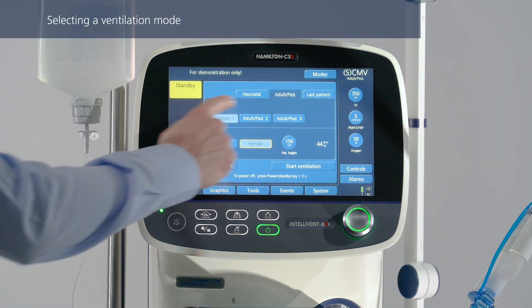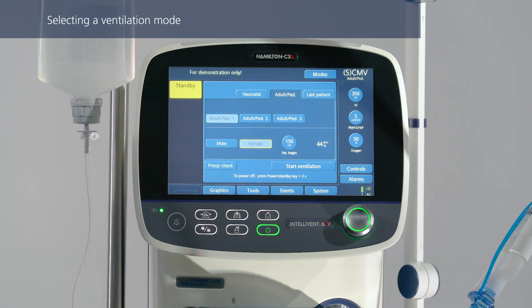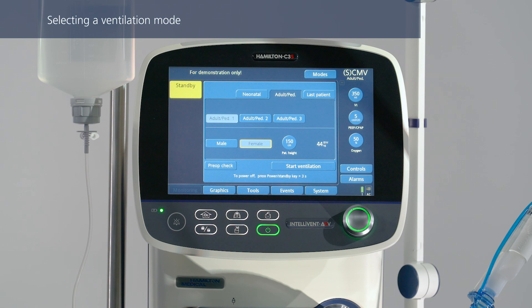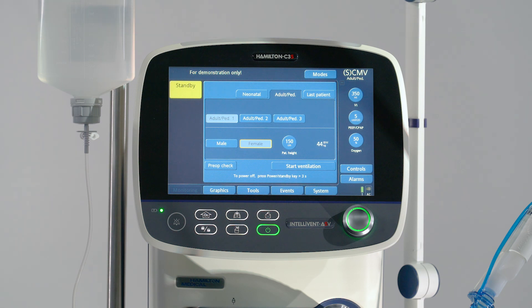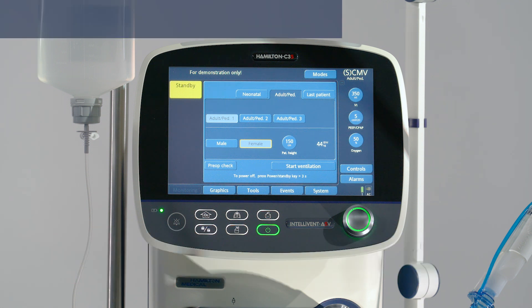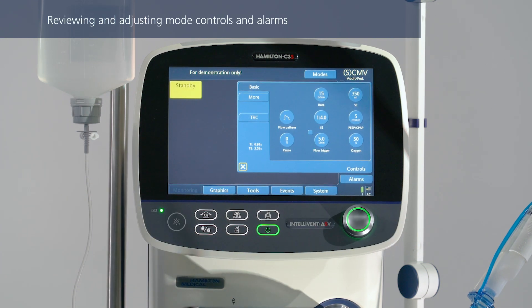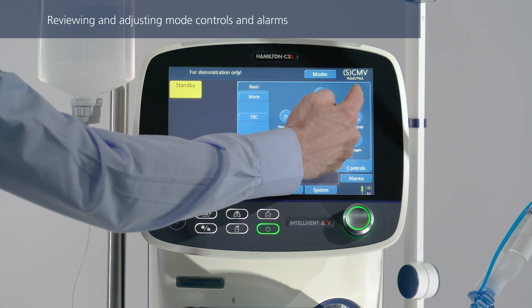For a new patient, you can pre-configure the ventilator quickly just by touching a quick setup button. Each quick setup defines a ventilation mode and all the settings relevant for that mode. For each of the patient groups, three different default configurations can be defined. Of course, you can always modify any of the settings. Review and adjust the control settings as needed.